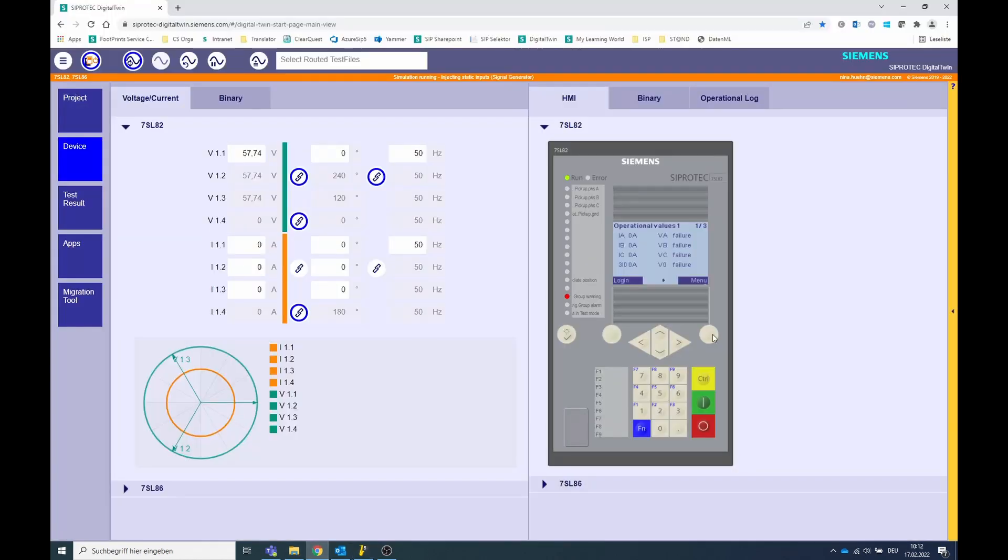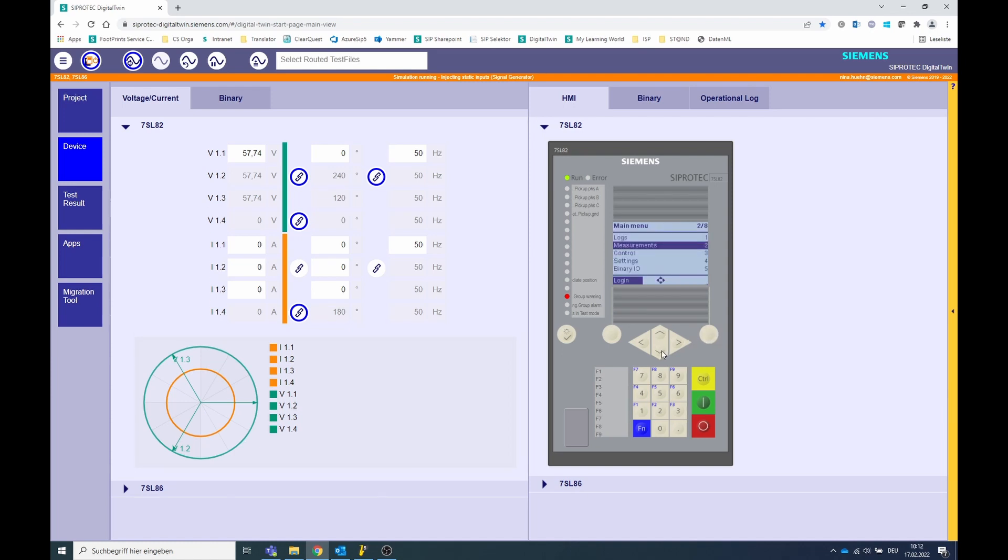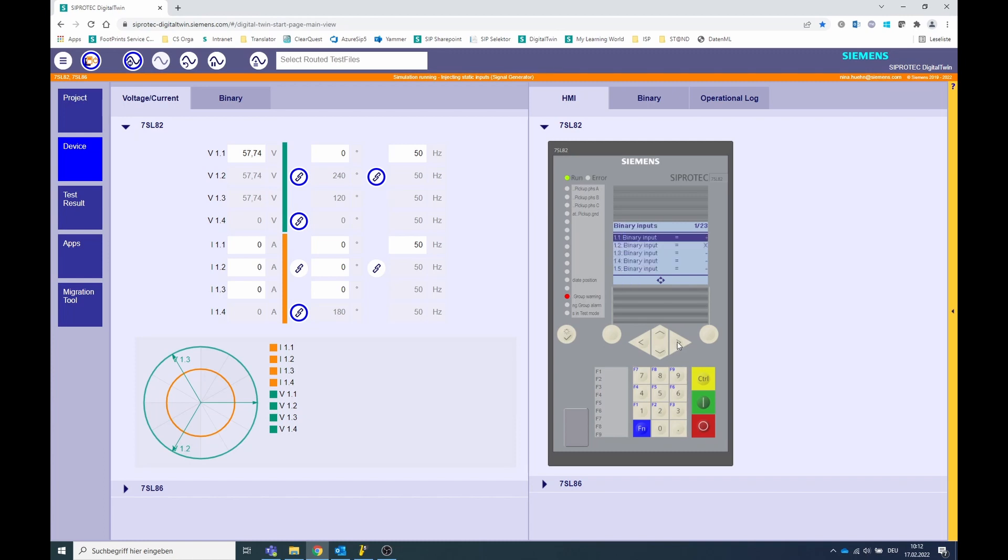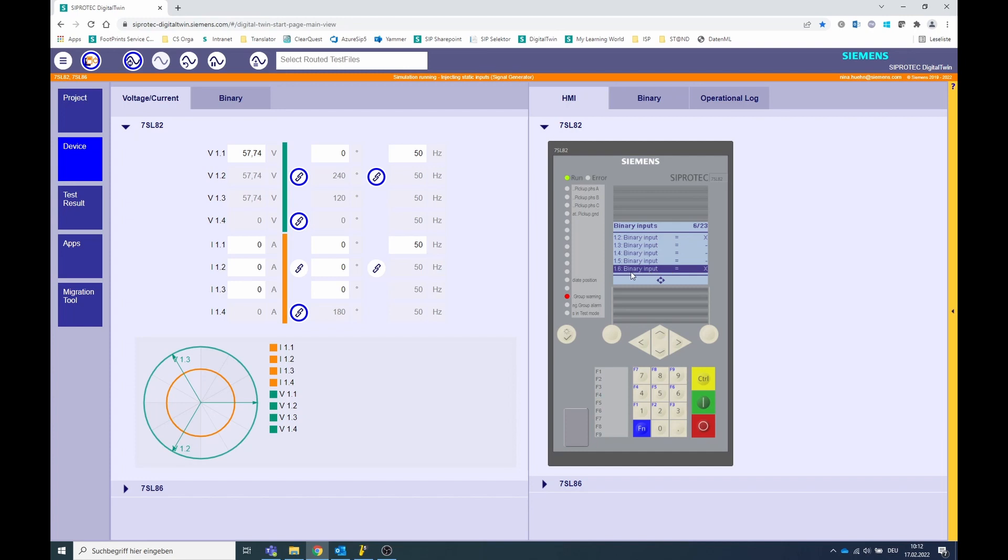Now go to the menu on the device display to menu item 5 binary inputs and outputs and choose the binary inputs. The status of all binary input signals is displayed here. We see that in this example, the binary input 1.6 is active. This means that the device detects a pickup of the voltage transformer circuit breaker.